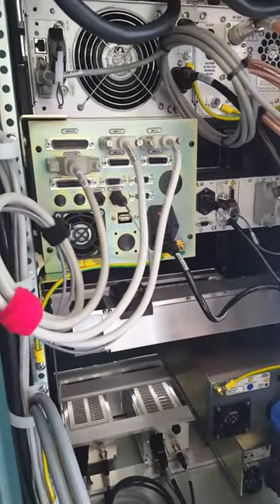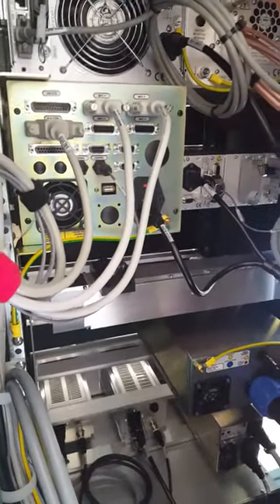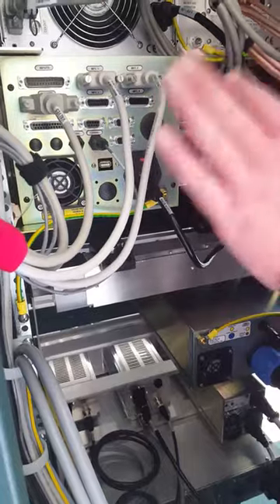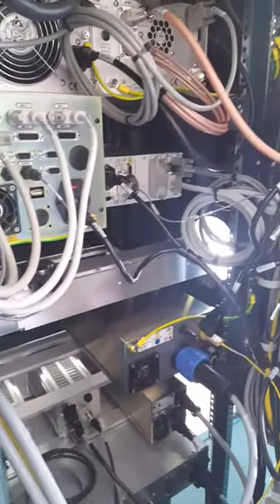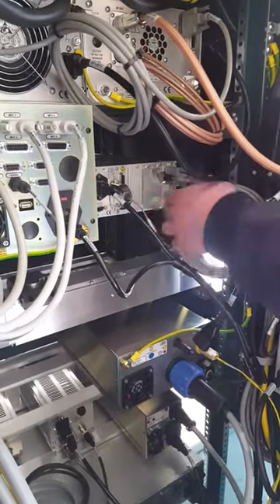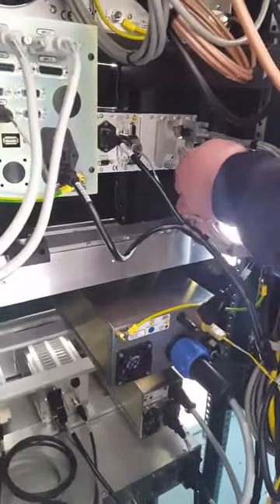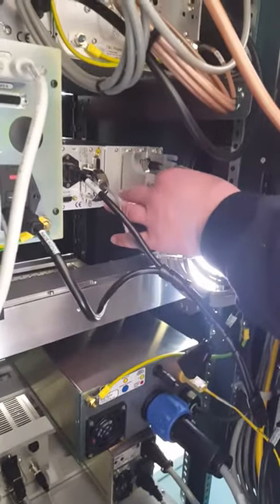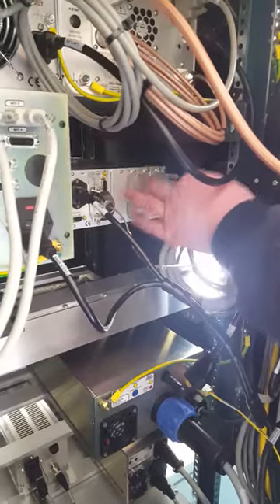This is just 24 volts power that is powering the load lock gauge. There's some room for expansion on this as well. Back of the gauge controller — each gauge has its own channel here. This is the ion gauge coming in here, this is the convectron gauge, and this is the baratron gauge — the process gauge.